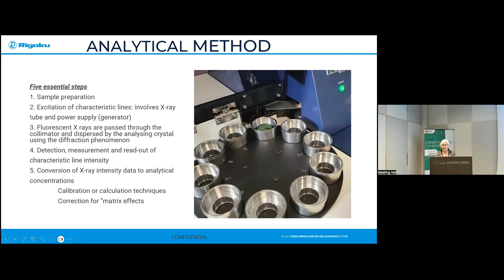So in this example, I showed you our smaller instrument. Of course, the bigger instrument, if you are interested, you can contact us. You can see that we have a Super Mini, which has a small sample changer of approximately 10 positions, and you can fit different sizes in here. So how do we perform the analytical method? Well, as I explained, we need a calibration. And in order to create a calibration, we can get calibration standards with a suitable range so that we can cover 95% of the natural distribution range to accurately and precisely measure the ground granulated blast furnace slag.